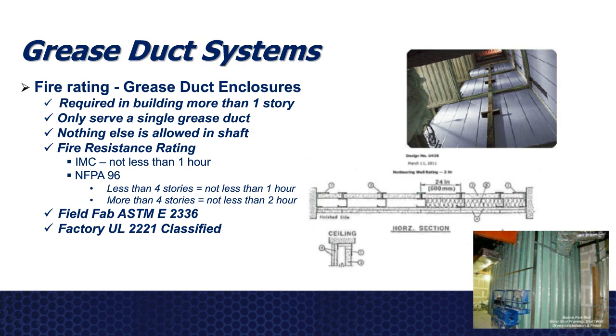So the fire resistance rating that shaft would have to have for International Mechanical Code, we would have to have at least a 1-hour fire-rated shaft to comply with the code. NFPA is going to be a little more stringent when it talks about fire resistance rating of shafts. It's going to tell you a building that is less than 4 stories, we can get by with a 1-hour fire rating. But a building that would exceed 4 stories would have to have at least a 2-hour fire rating for that shaft. Now, how do we get away from a shaft?